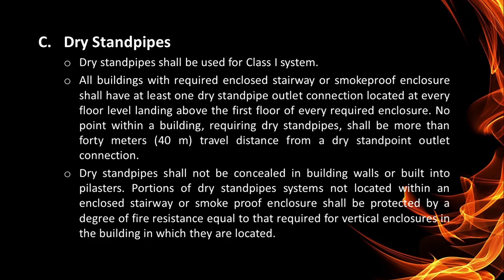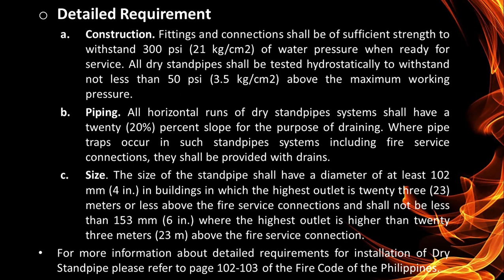Portions of the dry standpipe system not located within an enclosed stairway or smoke-proof enclosure shall be protected by a degree of fire resistance equal to that required for vertical enclosures in the building in which they are located. So, detailed requirements for installation of dry standpipes. First is the construction. Fittings and connections shall be of sufficient strength to withstand 300 psi of water pressure when ready for service. All dry standpipes shall be tested hydrostatically to withstand not less than 50 psi above the maximum working pressure.